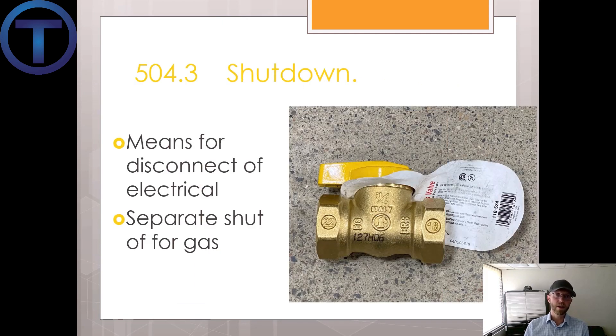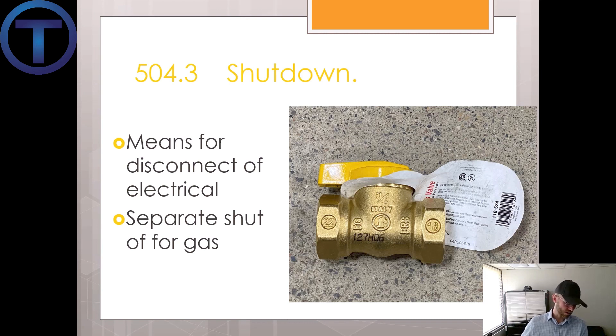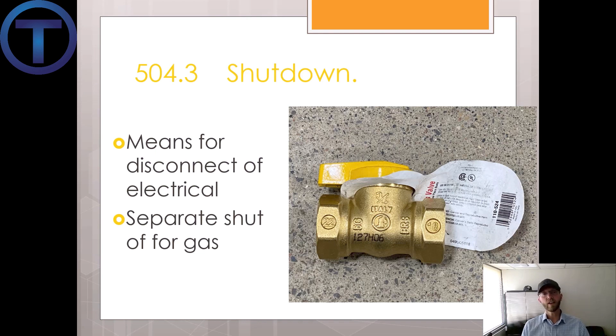504.3 talks about shutdown. A means for disconnecting an electric hot water supply from its energy supply shall be provided. So if it's electric, we have to be able to shut that off. A separate valve shall be provided to shut off the energy fuel supply for all other types of hot water supply systems — so if the water heater uses natural gas to heat, we have to have a separate shut-off valve for that appliance.